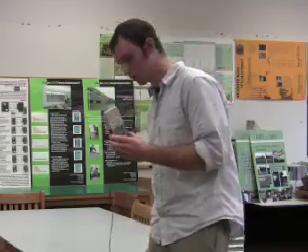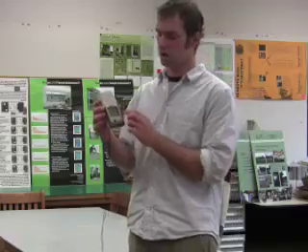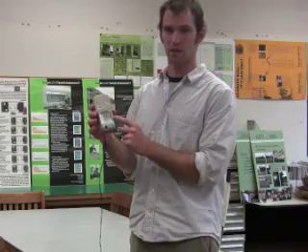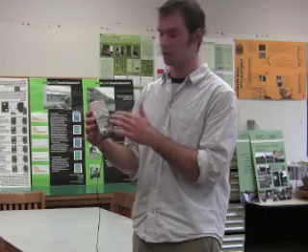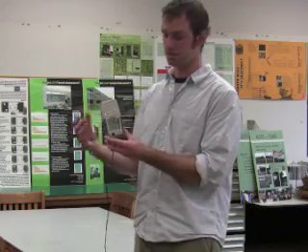And in your hoboware, when you download your data, each one single ppm will show up as 1 millivolt on the external channel. So then you can get a graph of CO2 over time in your hobo data.